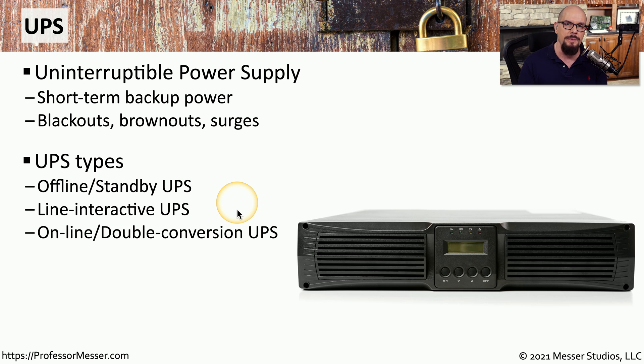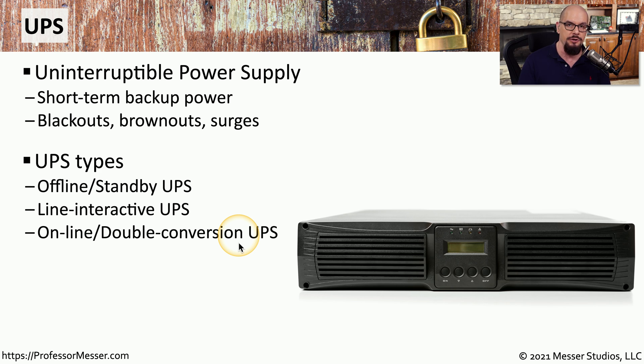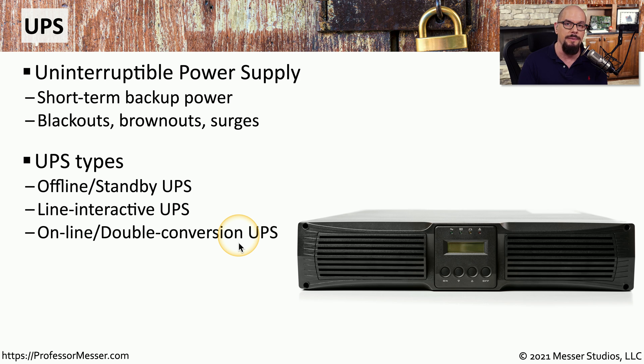The kind of UPS that's probably the most complex and most expensive is the online, or what is called the double conversion UPS. This UPS is always online and always providing power to your devices. And if the power does go out, there's no switching process because you're already on battery power.